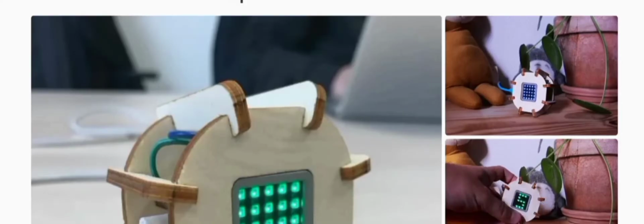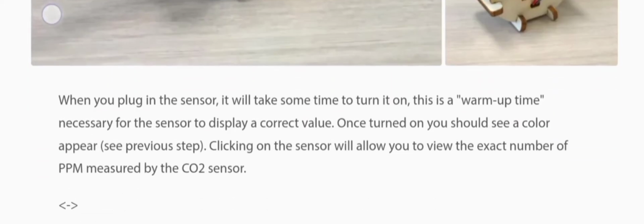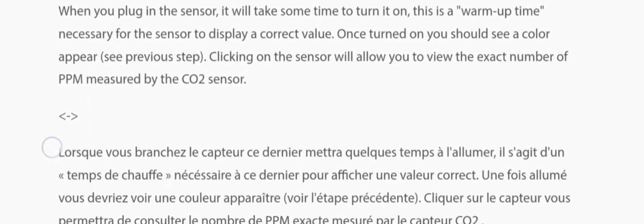Step 2, how the sensor works. When you plug in the sensor, it will take some time to turn it on. This is a warm-up time necessary for the sensor to display a correct value. Once turned on, you should see a color appear. See previous step. Clicking on the sensor will allow you to view the exact number of ppm measured by the CO2 sensor.